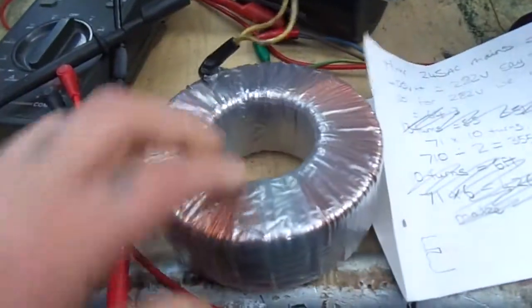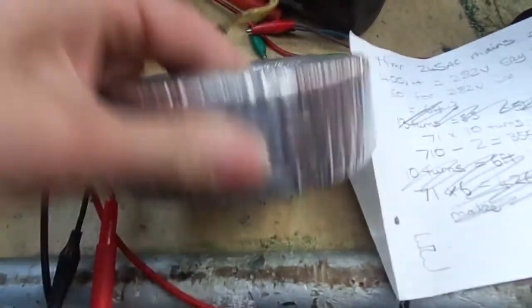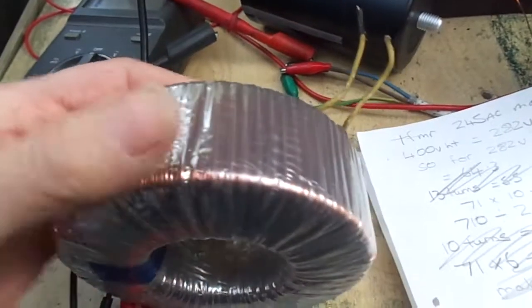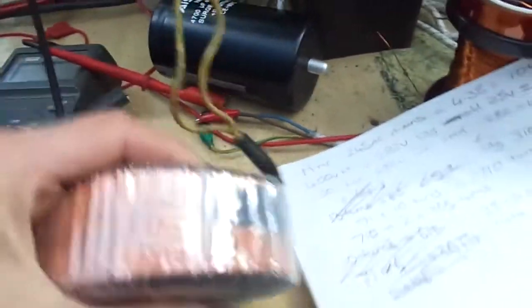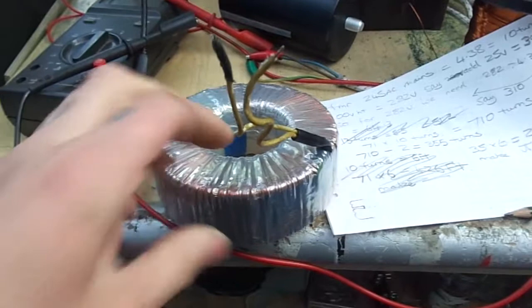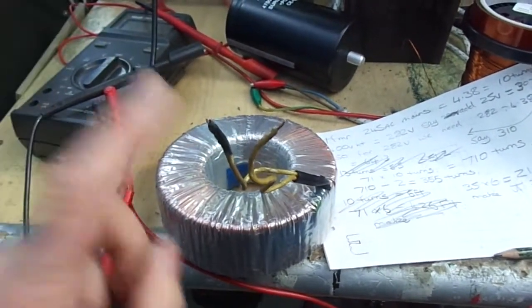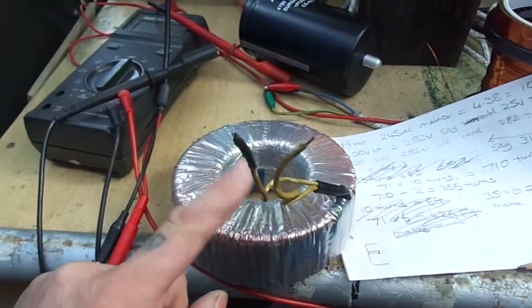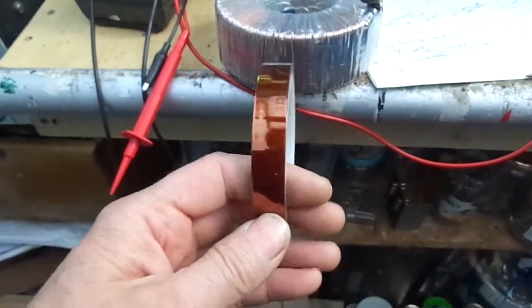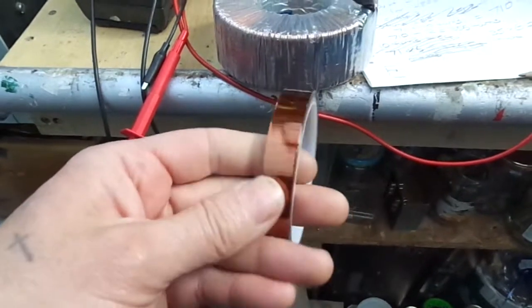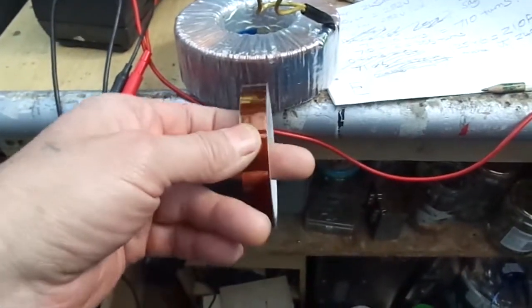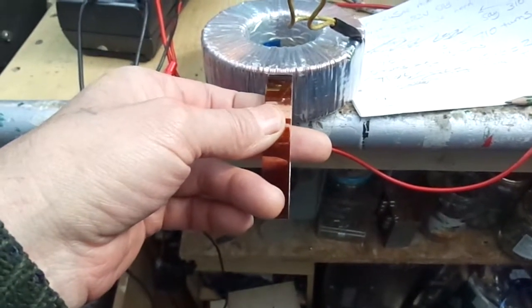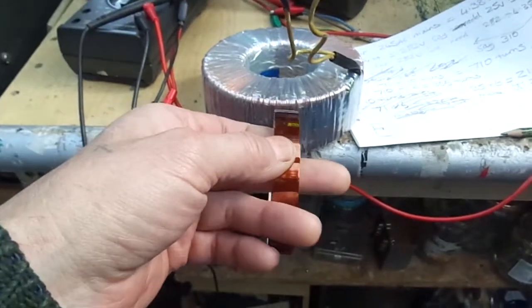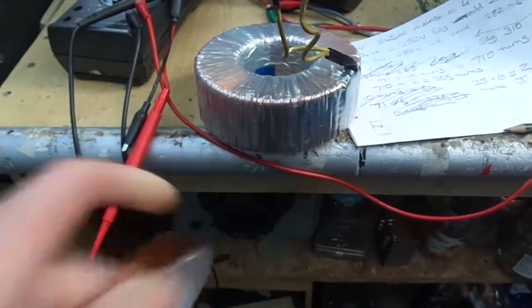So before I do that - as you see, this has already got some insulation between the primary, but it's probably, because this is used, got a few dinks in there, and I want to be absolutely sure, because obviously we've got a lot higher voltage than there was previously when this was wound. This had two 50 volts at 5 amps. So you can get this stuff called Kapton tape off eBay - well, you can in the UK, I think you can anywhere - it's about £5 a roll. So I'm going to put a layer of that over this secondary, and then I'm going to go and put on my heater windings, which I'll come to in a minute. Okie dokie.